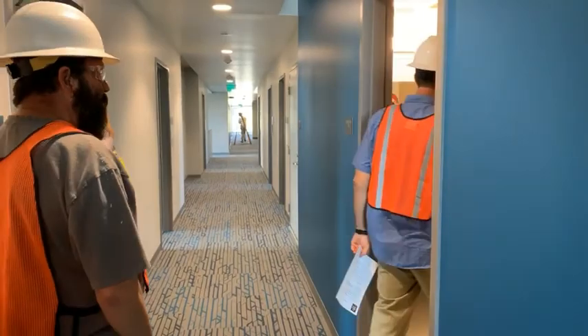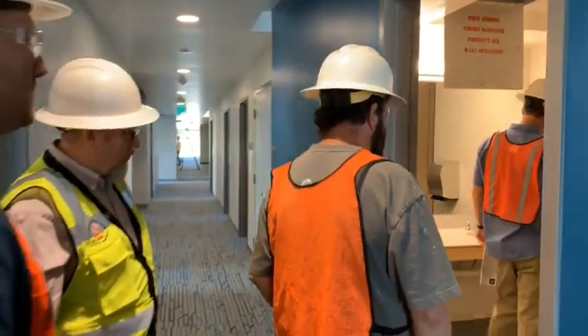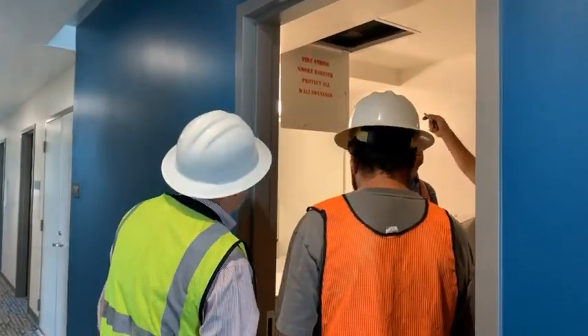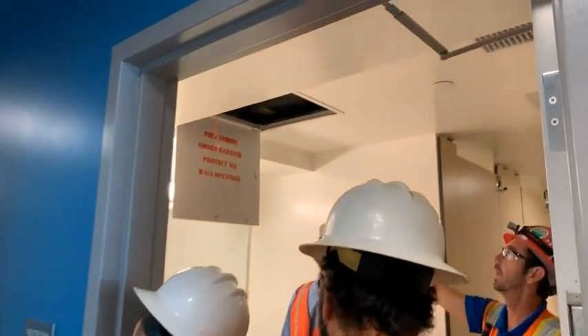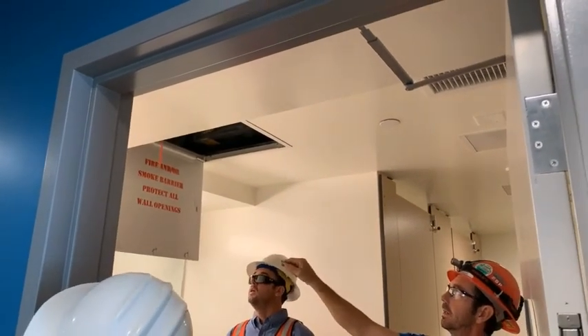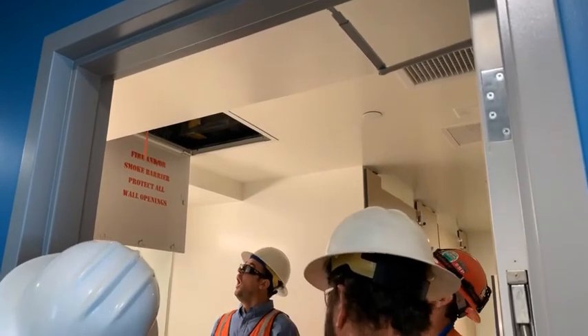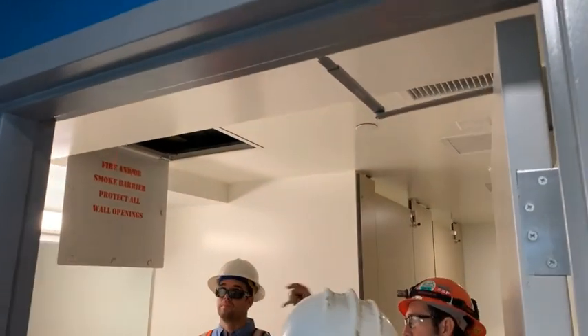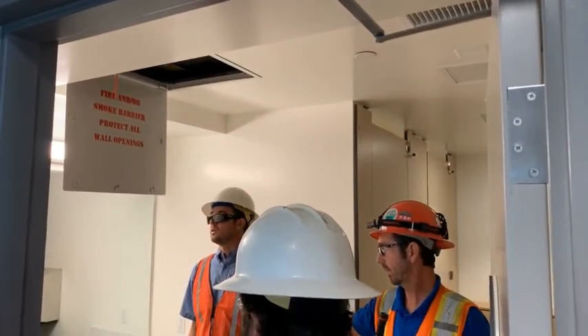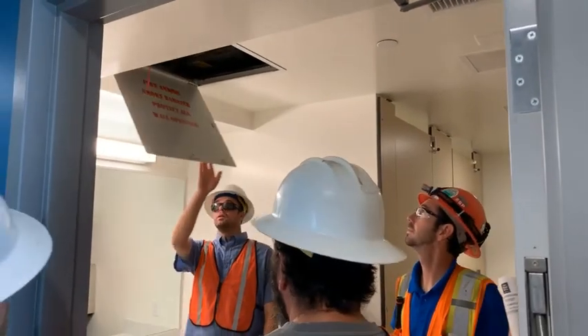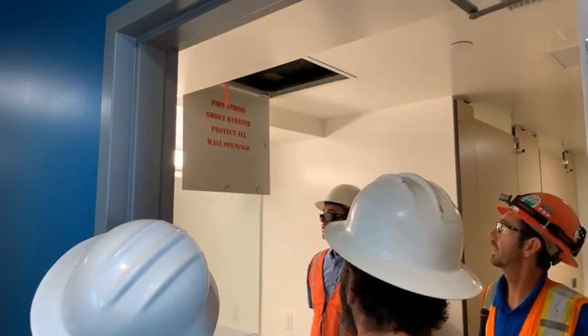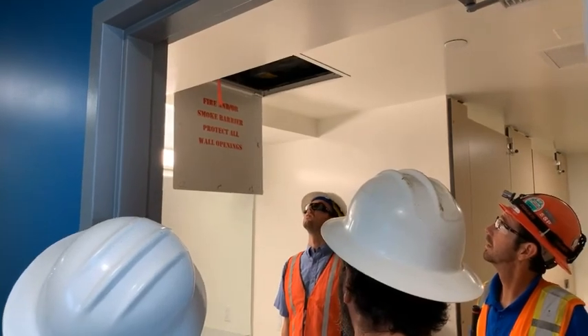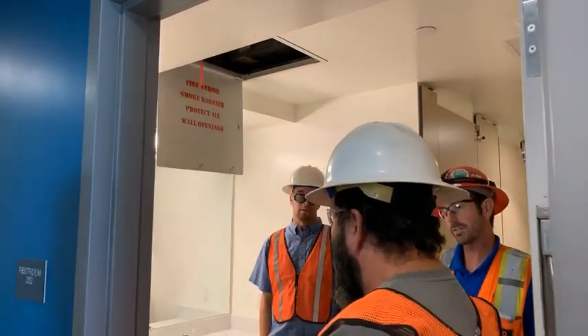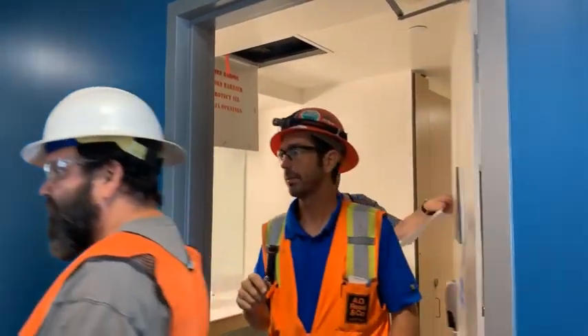Okay? Which is handicap accessible, so nothing is below here for their access. The pressure reducing valves will be up here in the ceiling. One access door here, one access door here for each one of the valves. Again, a shutoff valve on the inlet, and then downstream you'll just have to drain the fixtures down here. It works easier here than on the other one. I'm not sure why that was open. Okay, so overhead on the first two bathrooms would be the ADAs, and then we'll go look at the next restroom.